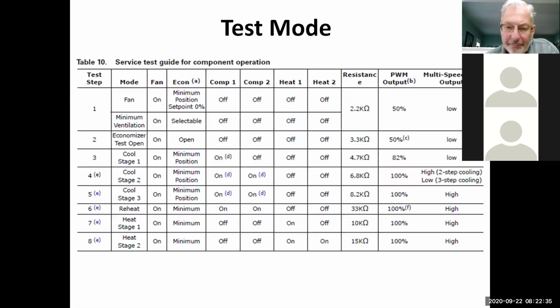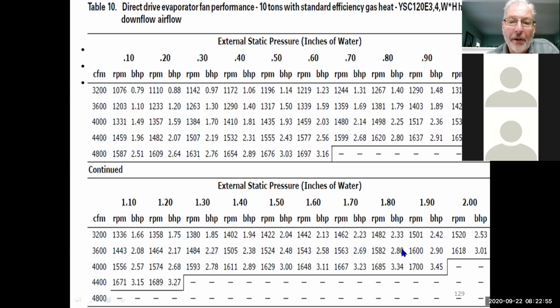So once you get your static, and again, when you're doing these units, make sure that we got it into this 100% fan mode. So make sure it wasn't a fan call or an economizer test. It had to be in a cooling call or a heating call to get to that 100% airflow. And just for this example, on this 10-ton unit, they come factory set at 5 volts DC. So on a 10-ton unit, we need 4,000 CFM. And in order to get to that 4,000 CFM at a 0.5 static, we need to be at 1,435 RPM, okay? That's our target RPM.